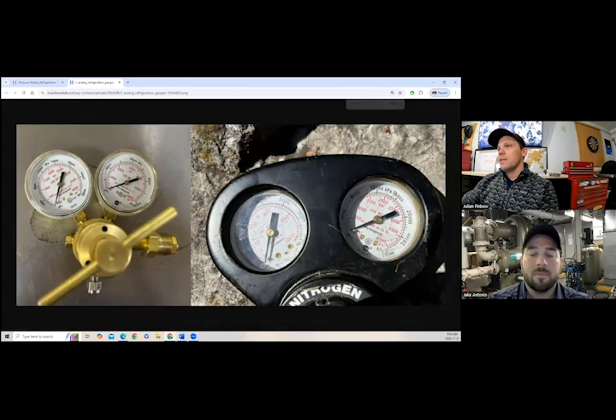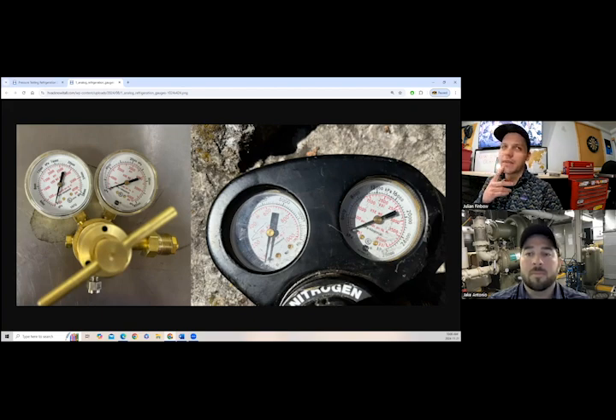So the pressures that you have on them, you have an inlet pressure from the bottle, and we'll stick with PSI. On the right side, you have an inlet pressure from the bottle. So a standard nitrogen bottle is like 2500 psi if it's a fresh bottle. It's kind of all over the place, anywhere from 2000 to 2500. I think the standard's like 2200, but it's going to be up around that 2000 psi mark. So I'll mark this up.